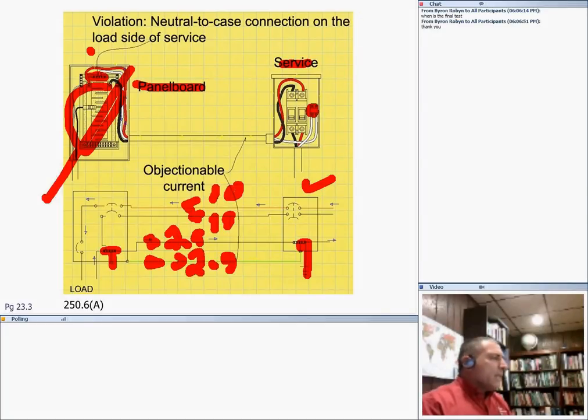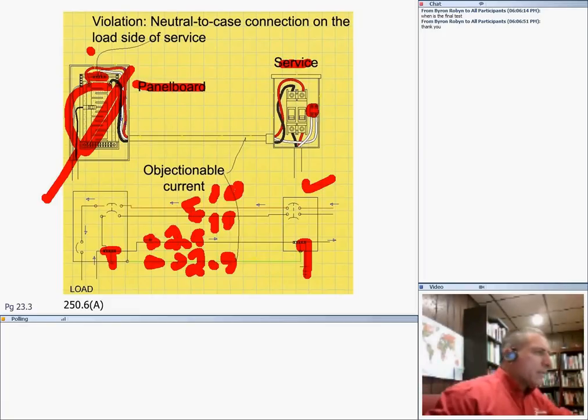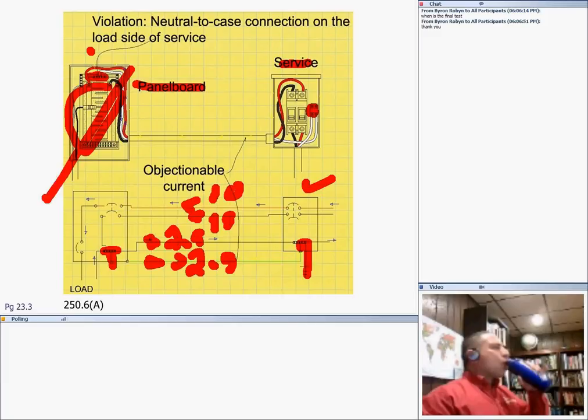So the equipment grounding conductor, if you bond right here, will act as a neutral conductor, and it carries current all the time, unbalanced current. Of course, that's a safety hazard. We don't want that to happen, so that's why we bond only at the service. Any questions, guys?